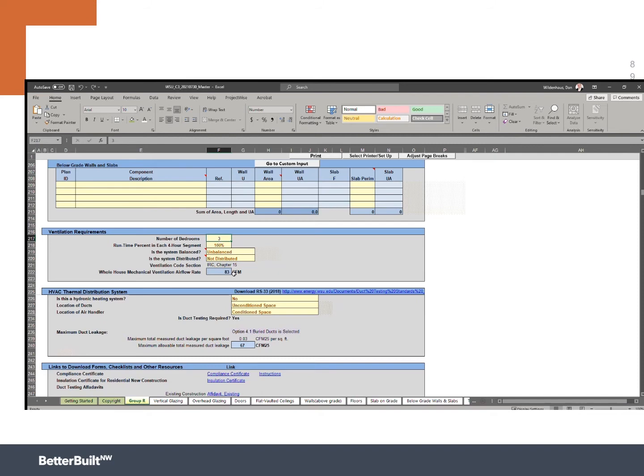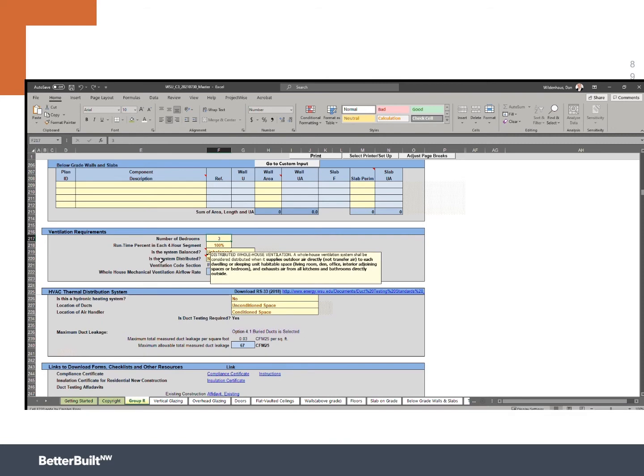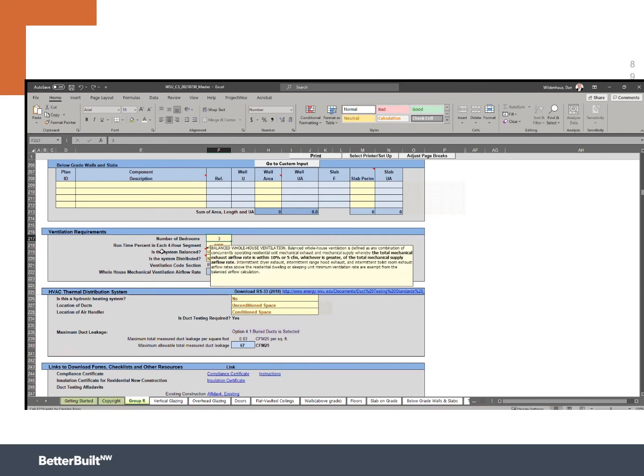So here the first thing we're thinking about is how often is this going to run? Now, if you're just using an exhaust fan, if you've got a really high quality Energy Star exhaust fan that does not make a lot of noise, your best bet is probably just to let the thing run all the time. In fact, the number one way that ventilation systems fail are when people turn them off. So we'll talk about other things later, but 100% we'll show you what happens if we didn't do 100%. As I hover over some pop-ups will come and explain a little bit more about the difference between a balanced system and a distributed system.